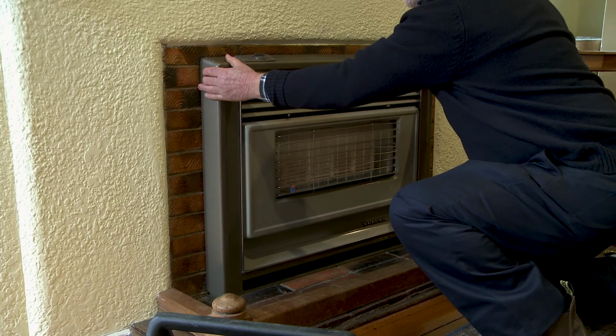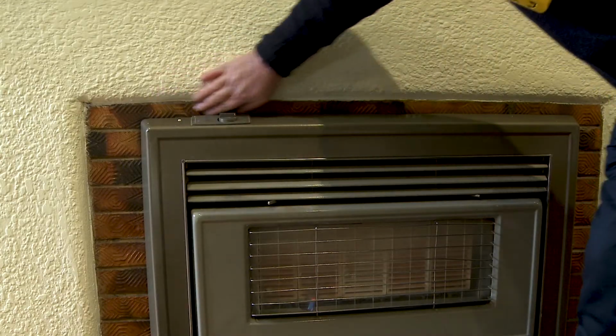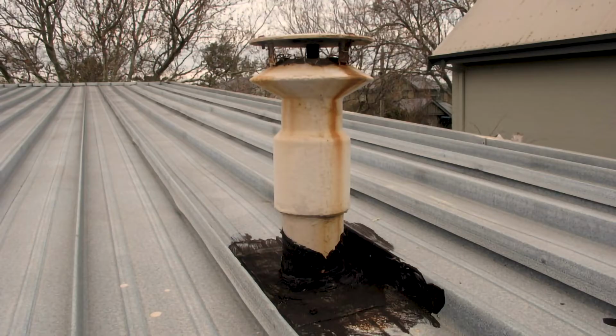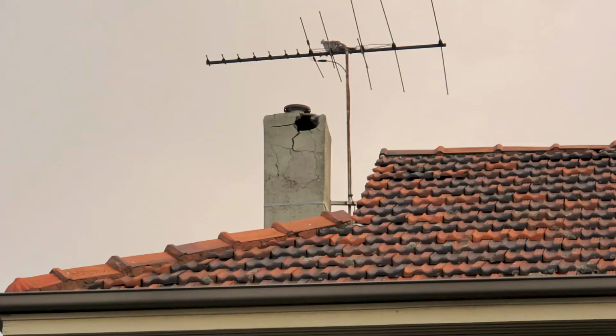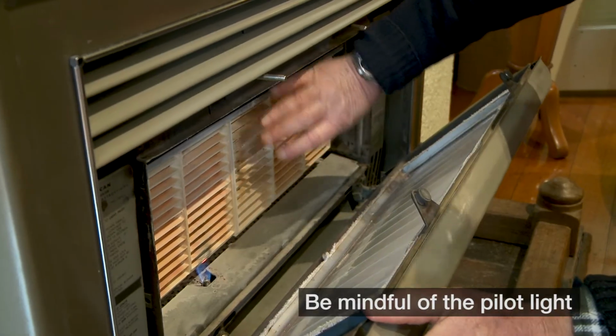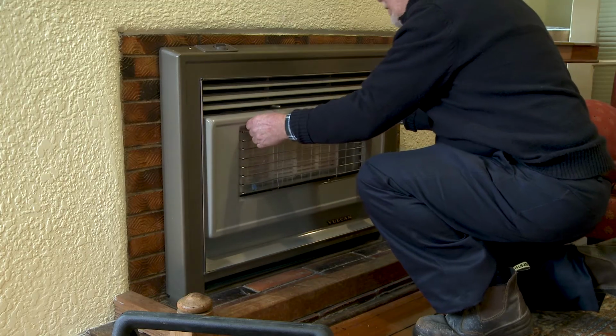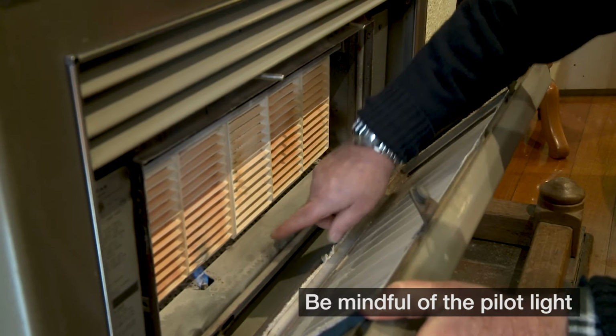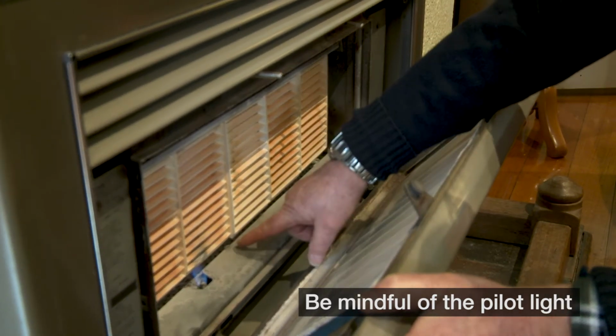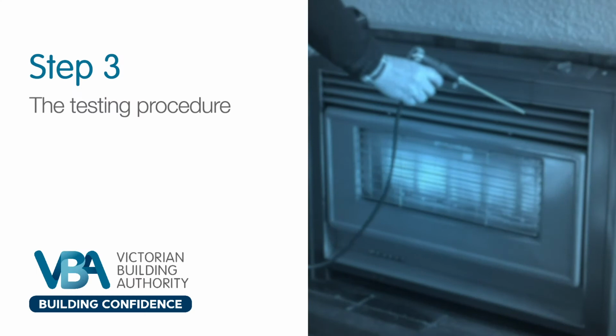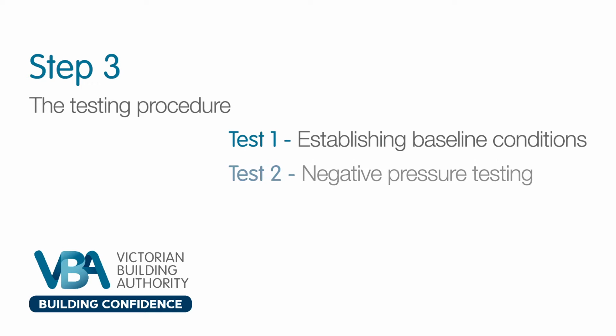Step 2. Inspecting the appliance. Look for signs that the unit may be unsafe, such as scorch marks, soot, or cracks or blockages in flues or chimneys. After you've finished an overall inspection and the appliance appears safe, you can move on to testing, or you may decide to clean the appliance now while it's still cold. Step 3. The testing procedure. Testing is divided into 3 equally important parts: establishing baseline conditions, negative pressure testing, and spillage testing.